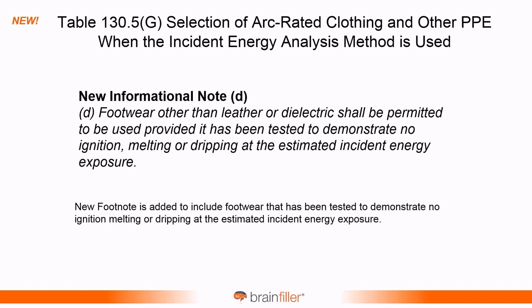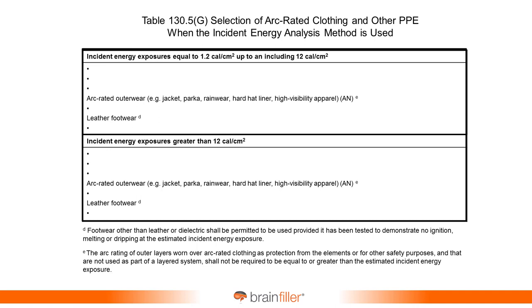Another is about footwear. In the past, it's been permissible to wear leather footwear or dielectric footwear, and that was really all that was mentioned. And now there's an informational note that states footwear other than leather or dielectric shall be permitted. So you can use footwear other than these two types, permitted to be used, provided, oh, there's a catch, it's been tested to demonstrate no ignition, melting, or dripping at the estimated incident energy exposure. And so that's a new informational note also added to the table for selecting arc-rated clothing and PPE, and also for the PPE category table.